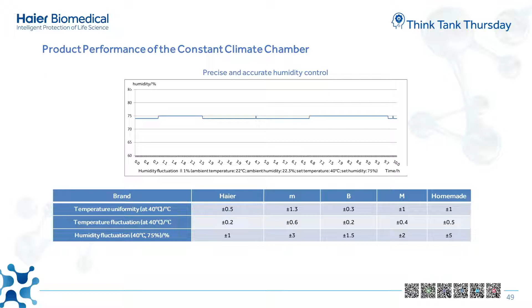When the ambient temperature was 22 degrees and the ambient humidity was 22.3%, we set the instrument to 40 degrees and 75% humidity. A 27-point test was conducted according to the DIN standard. You can see the details. From this chart, it can be seen clearly that Haier Biomedical's performance in temperature and humidity is better than other brands.